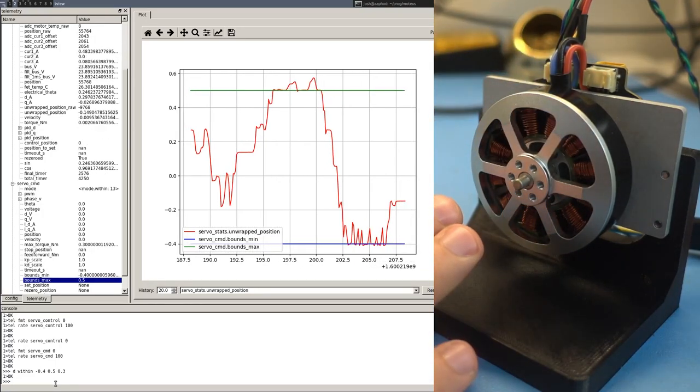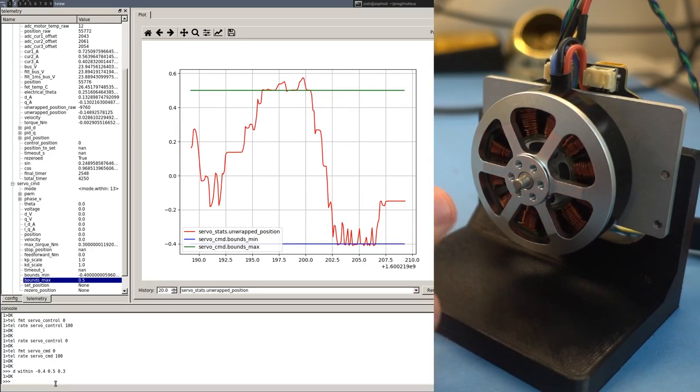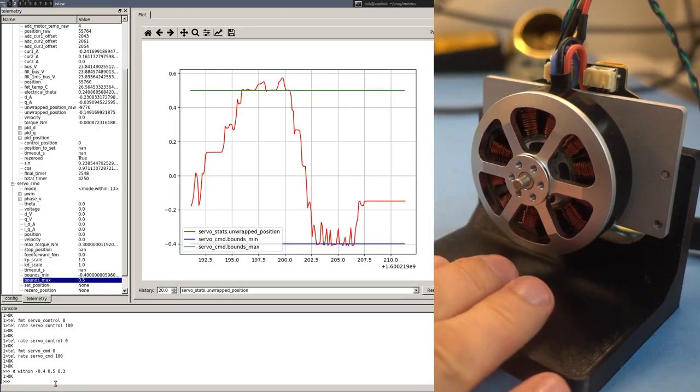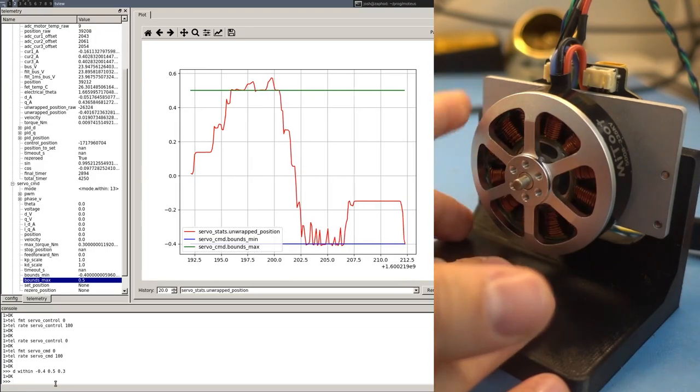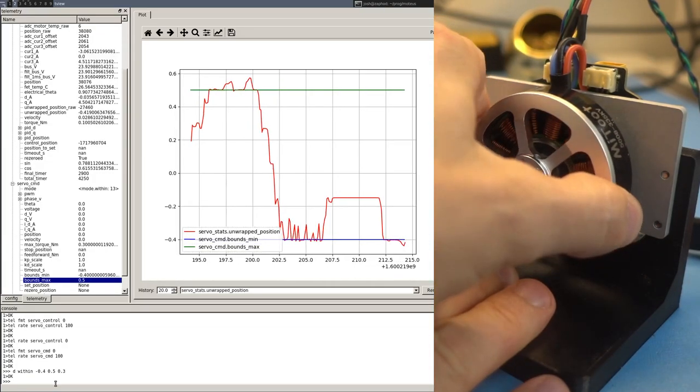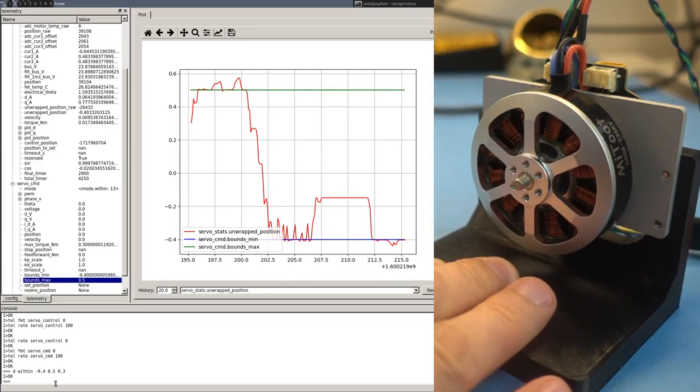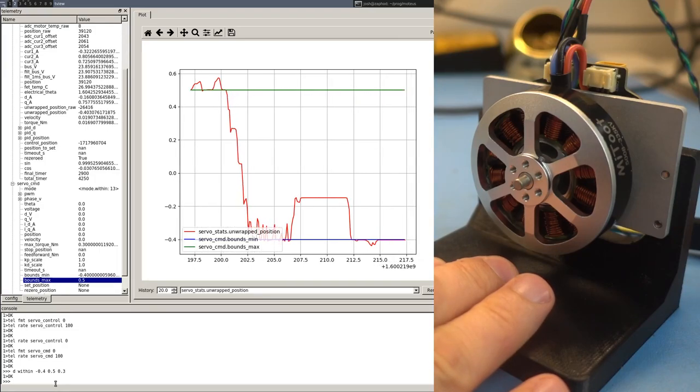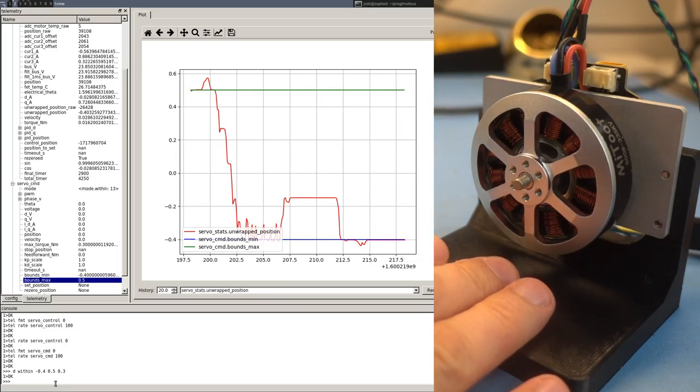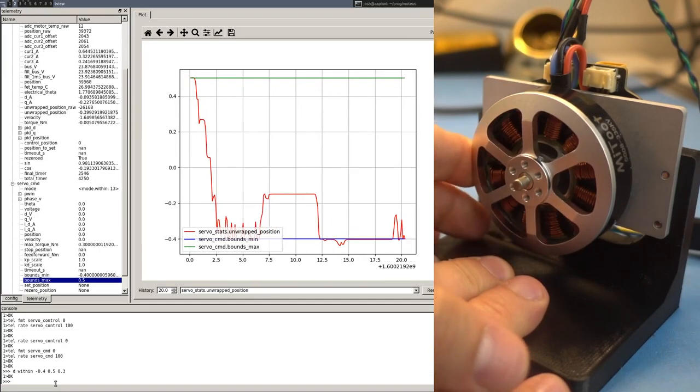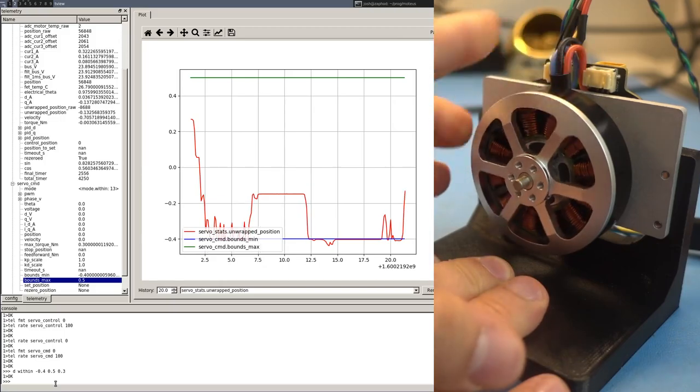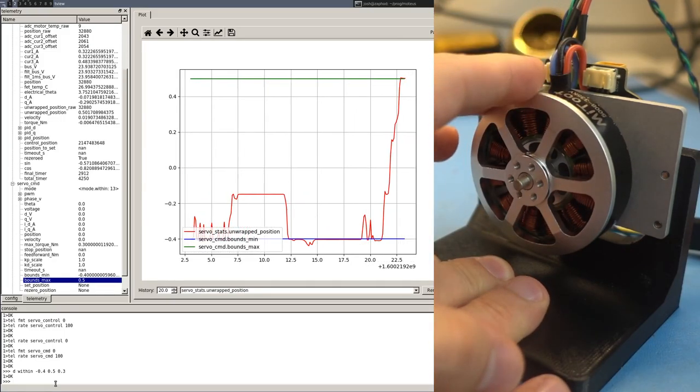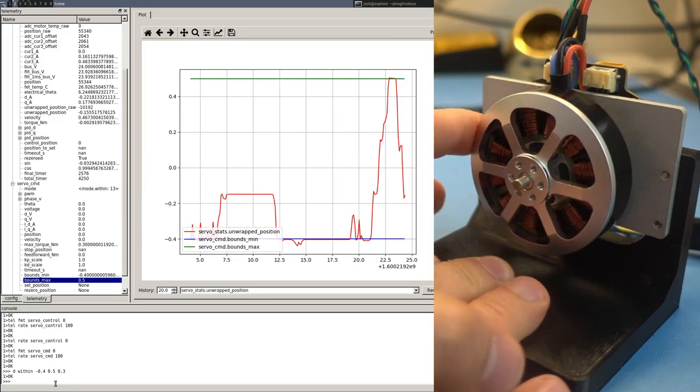Now, the advantage of this new control mode is that the wall behavior operates at the full control rate of the moteus controller. You could implement something similar using a higher level controller, but it wouldn't have the same instantaneous response that running it at the full 40 kilohertz does.